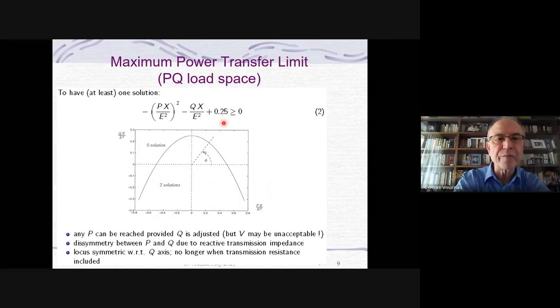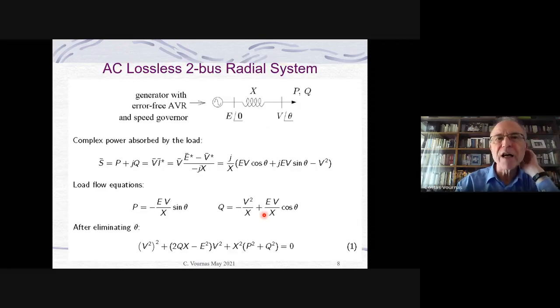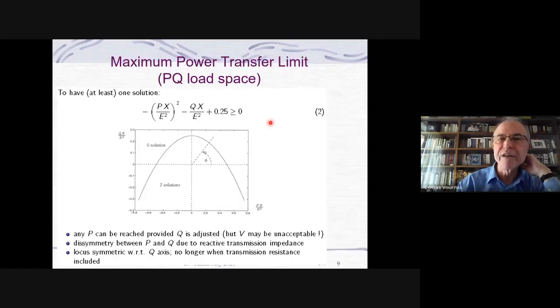And this condition I have put in a figure, and so as not to have P and Q in watts and vars or per unit, I take them as a percentage of the short circuit power. And by short circuit power, I mean if I have V equals 0, the current is E over X. The short circuit power in an AC system we call E times the short circuit current. So E times E divided by X, E squared by X, is the short circuit power. So I have the active power as a percentage of short circuit power, and the reactive power as a percentage of short circuit power.